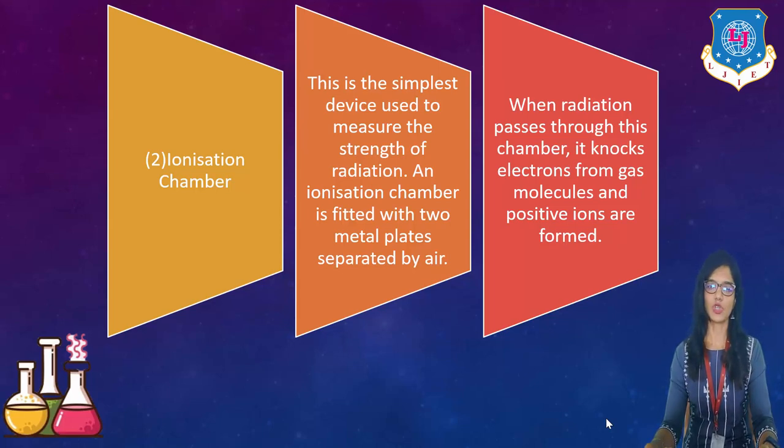Our next one is ionization chamber. So this is the simplest device used to measure the strength of radiation. Here you can measure the strength of radiation. An ionization chamber is fitted with two metal plates separated by air. And when radiation passes through this chamber, it knocks the electrons from gas molecules and positive ions are formed.